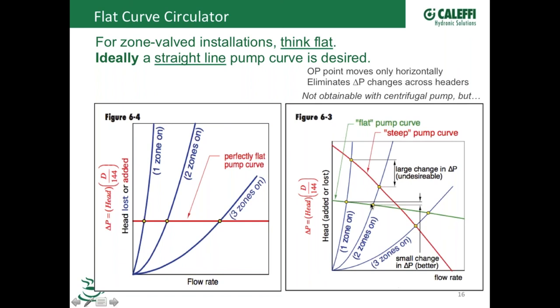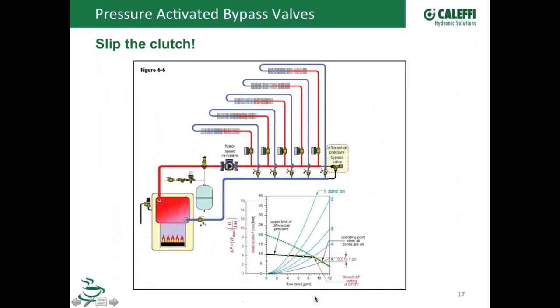Now, there's a couple other things you can do when you choose to zone with valves that can help you with a system like that. One is a device called a differential pressure bypass valve. You might see it called a PAV, pressure activated valve, or PAB, pressure activated bypass valve. But basically, it's like a spring and a flapper in here, a plunger, almost like a pressure relief valve.